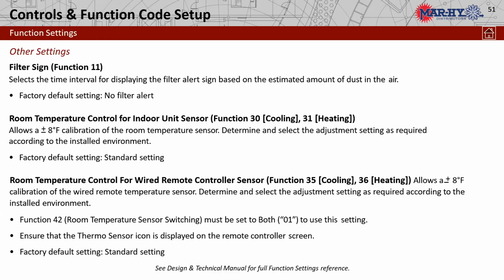So it'll tell you, okay, turn this dip switch to on or turn this function on, and then we're actually going to make the changes in another function number. So they kind of work together. One function will say, yes, we're going to enable, and another function will actually give you the ability to make the changes or set the parameters for that function, if y'all get what I'm saying.